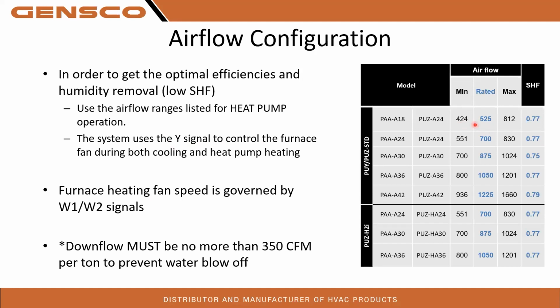We do have minimum and maximum rated airflows in each coil, so please make sure to match that up with your furnace. And you can see we got targeted ones. If you're using a downflow furnace, do not exceed 350 CFM. What can happen is you can end up getting too much airflow across that thing and blowing water off the coil and into your ductwork, flood out your house, whatever it may be. Not a good situation. Don't exceed that 350.